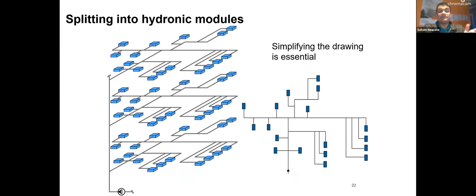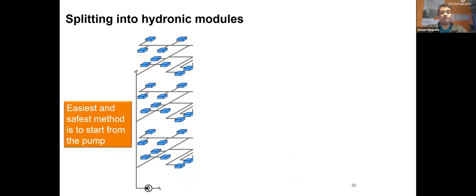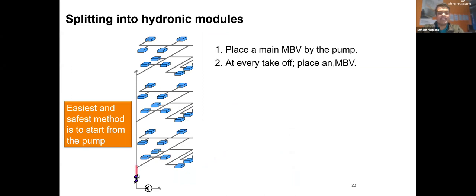So this is just the simplified version of the drawing you saw, the plan that I showed earlier. So, simplifying is important. It's just easier, much better for us to look at. So once we do that, we start basically placing manual balancing valves to create modules, okay? So what we'll do is we'll place a manual balancing valve by the pump. So that's the first manual balancing valve we place by the pump. And then we'll follow the pipe with the main flow, and at every takeoff, we'll place a manual balancing valve, okay?